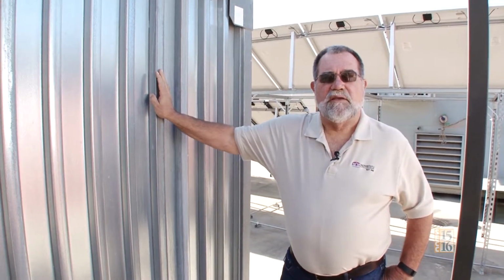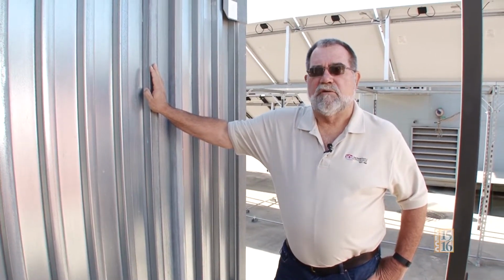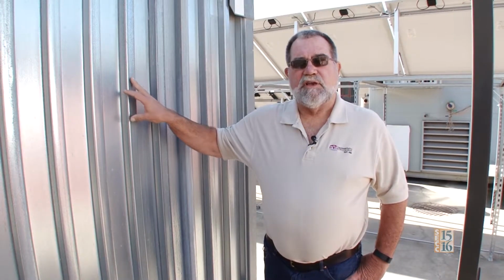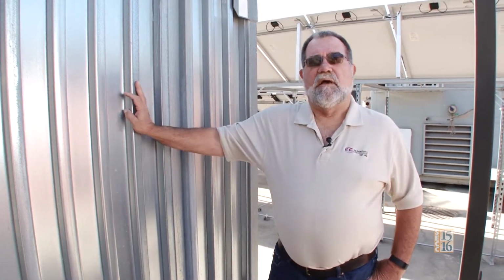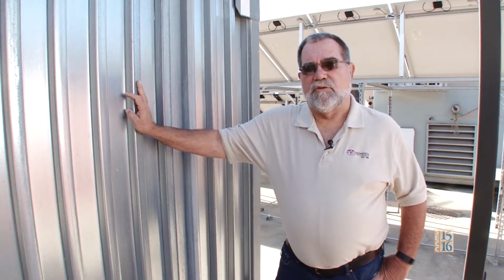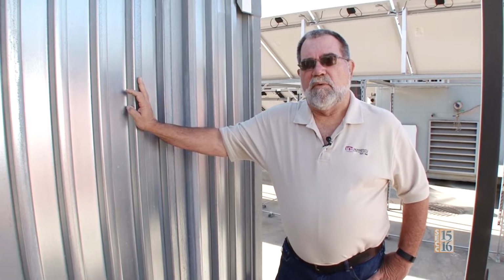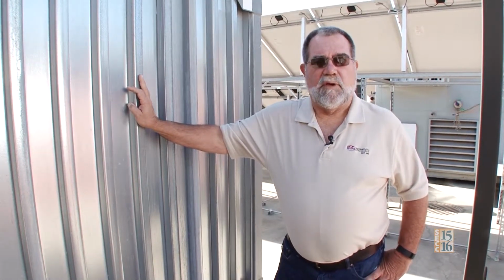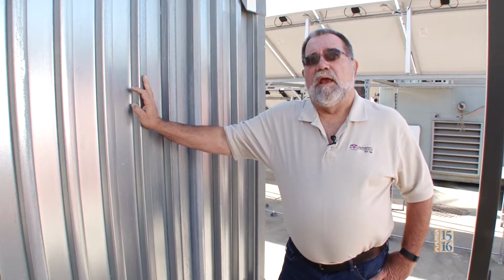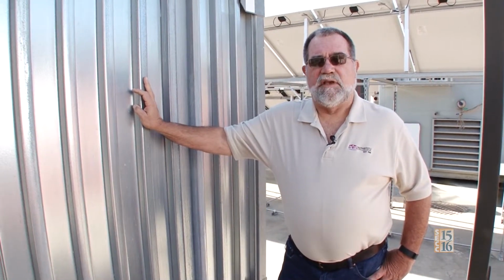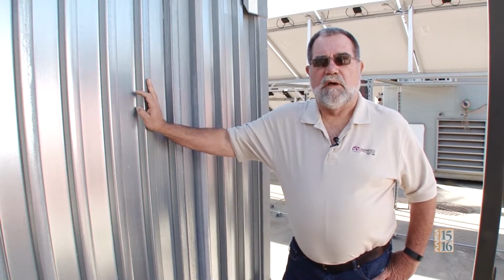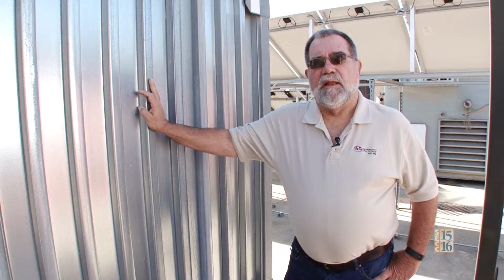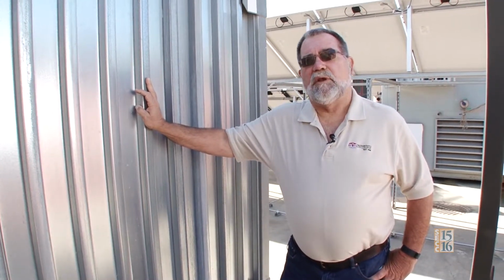Our system goes down to 19 degrees, that's the shutoff point for our chillers. This is inside this container, filled with water that has a glycol solution running through tubes, and the tubes are surrounded by non-treated water, meaning no glycol, so it freezes at 32 degrees. We freeze the water at night when electrical rates are low, then in the afternoon we harvest the ice by running chill water through it, and that ice cools the water so we can cool the building.